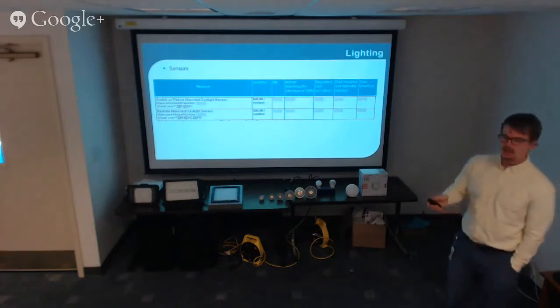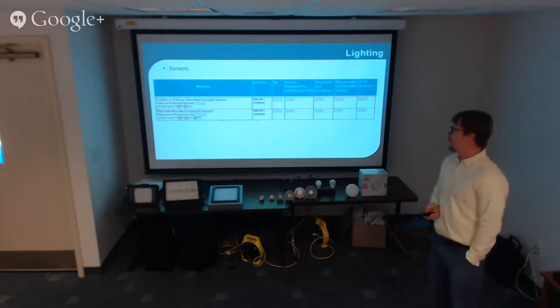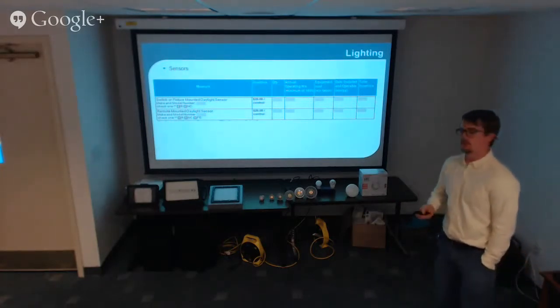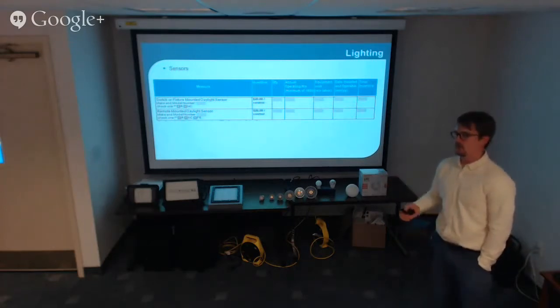So sensors, on the application in the past, we've had motion sensors that were good for $20 or $40. Now we've added daylight sensors, so switch mounted to the fixture or remote mounted for $20 a piece. One caveat to that is if you do use motion sensors, you can't use a daylight sensor in the same application and get credit for both. So you can only get credit for one.